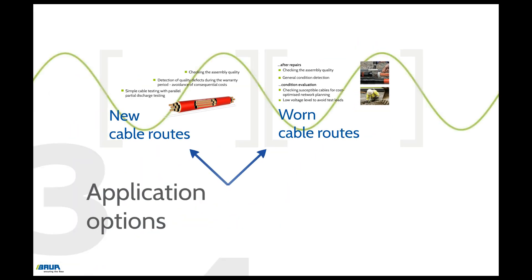Measurement with a sinusoidal voltage of 0.1 Hz forms the basis for efficient and meaningful cable diagnostics in all fields of application. Since this represents the same voltage shape as that used in actual mains operation, measurement results are provably highly comparable, which is a significant advantage of the VLF 0.1 Hz sinusoidal method. Furthermore, the cable route is not exposed to unnecessary loading in comparison to square wave or similar voltage shapes, which is a particularly important and beneficial aspect in the case of worn components.